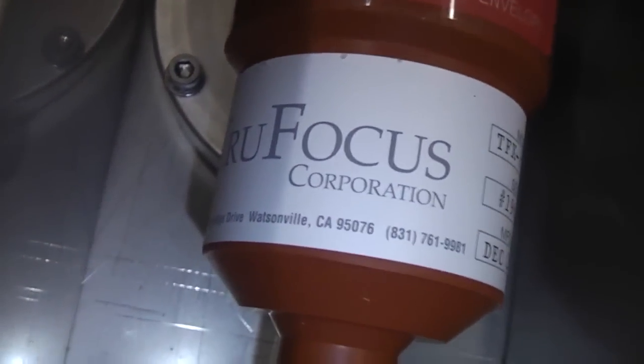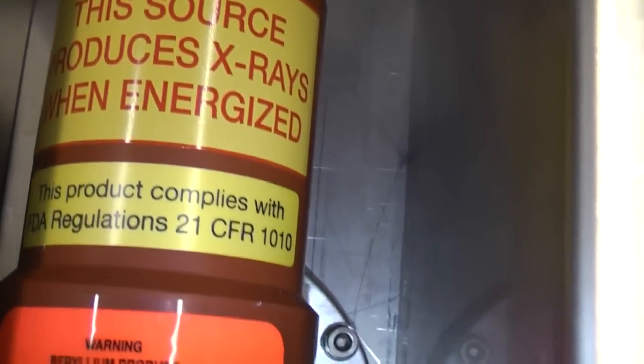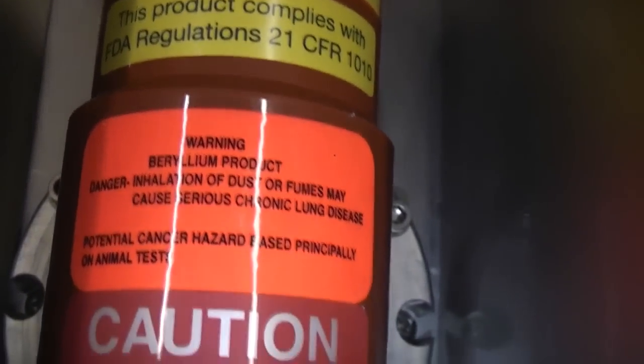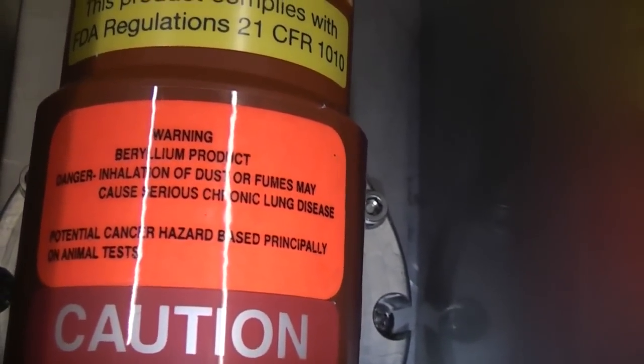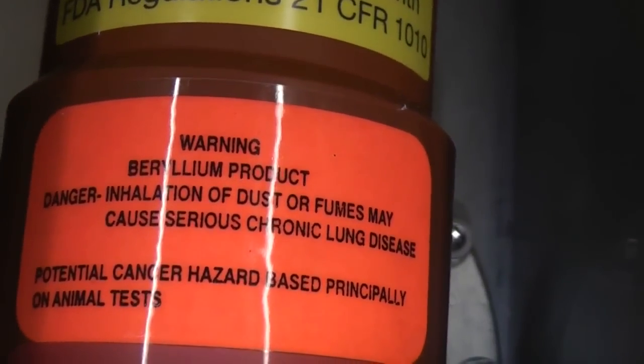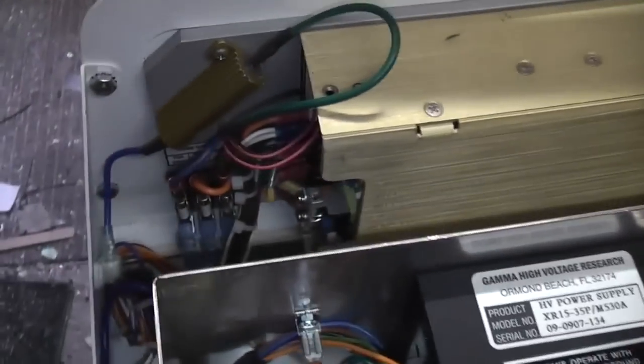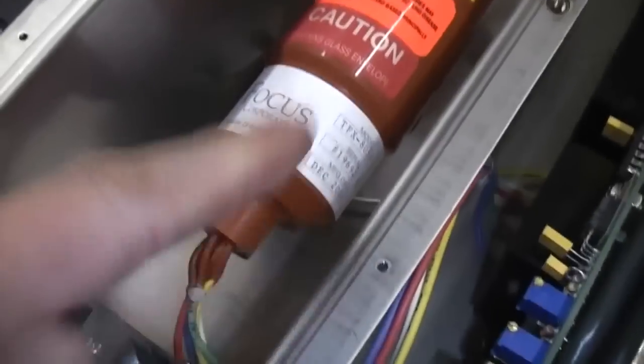This is made by a company called TruFocus Corporation. Lots and lots of warnings, X-rays and stuff, but also because it's a soft X-ray device, it's got a beryllium output window, so it's warning about the toxicity hazard of the beryllium on there. One thing I was a little bit surprised at, as far as I can tell, there doesn't seem to be any interlocks on this cover. I probably wouldn't expect one on here, but even this top cover, which just comes off with 4 screws, I can't see any sign of any interlocking to stop you just pulling all the covers off and firing it up, which I thought was slightly odd.